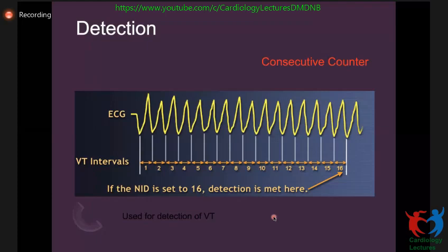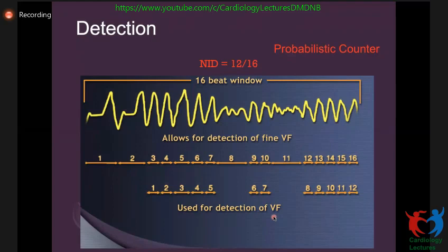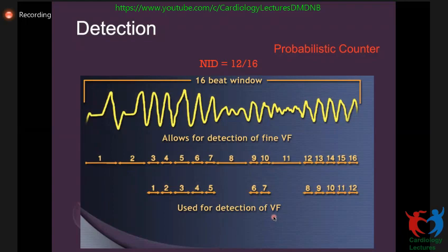This is a consecutive beats counter — 16 beats in a row come in fast and the detection criteria is met, then the device classifies it as VT or VF. For the probabilistic counter, you can program it at 12 of 16, 8 of 10, or 10 of 20 — counting through the window and if the required number of beats meet the fast rate criteria, it detects as VT or VF.